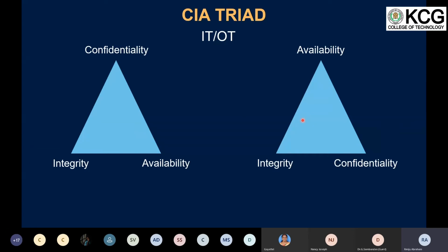Data integrity is also extremely important in control systems. If the operator screen in the control room does not accurately represent what is actually going on at the lower level, where the physical devices are connected, there could be a significant impact on operations or even on the safety of personnel or equipment. Confidentiality usually has a low priority in ICS, though there may be some scenarios where intellectual property resides on the plant floor or on an engineering laptop. Most operational information or tags, such as temperature, fill level, vibration, or speed, remain unencrypted because their value is short-lived.